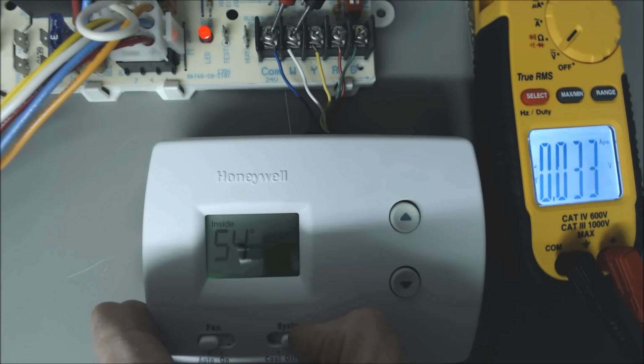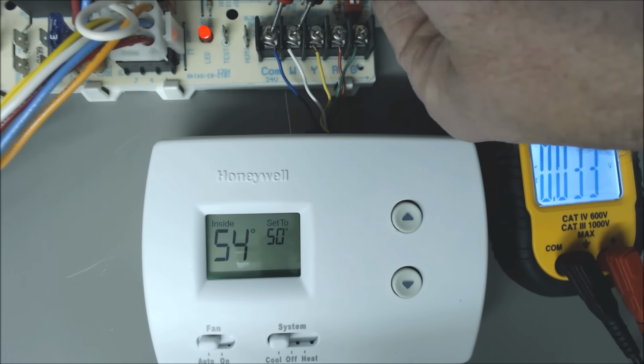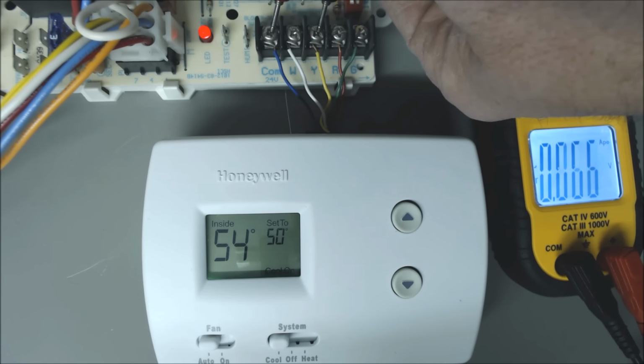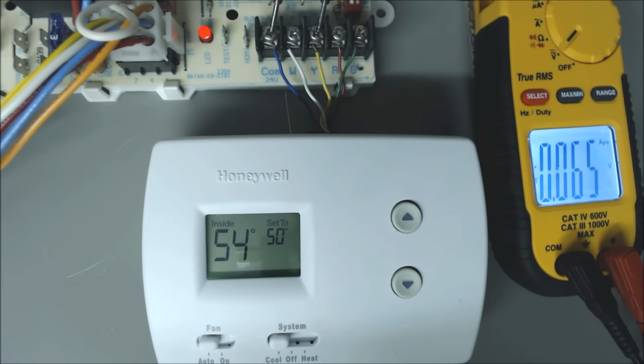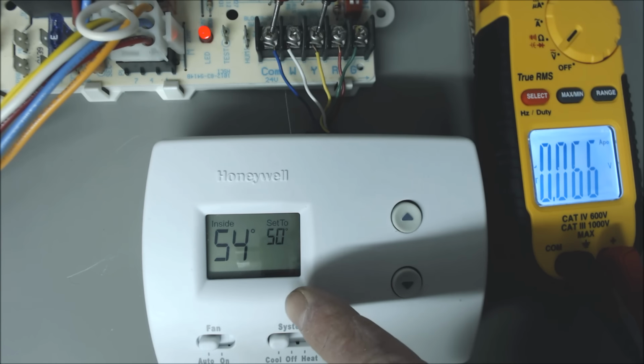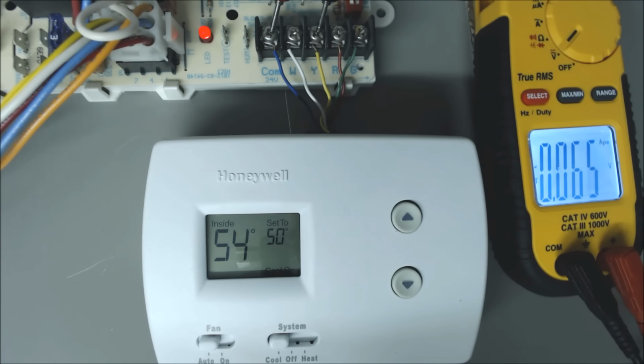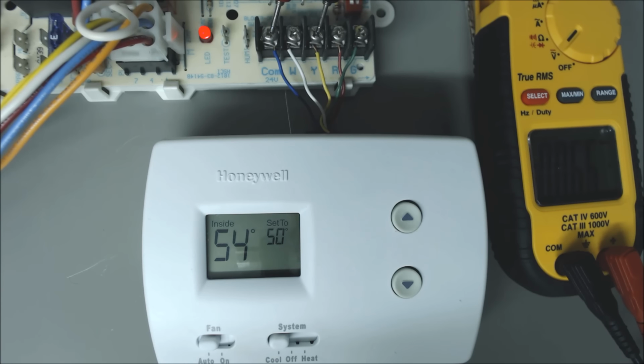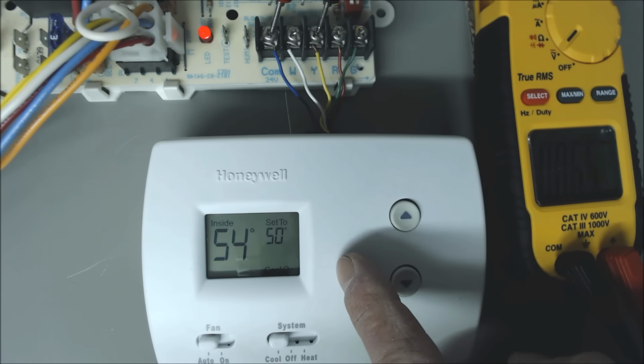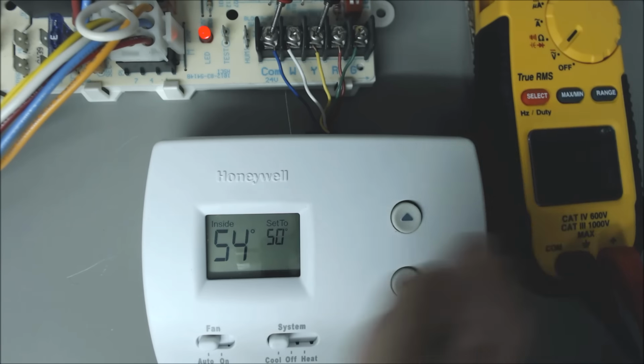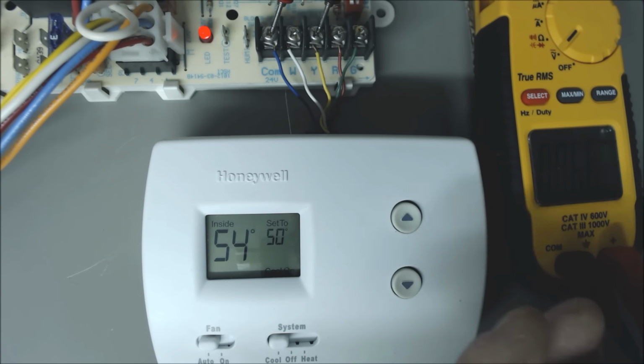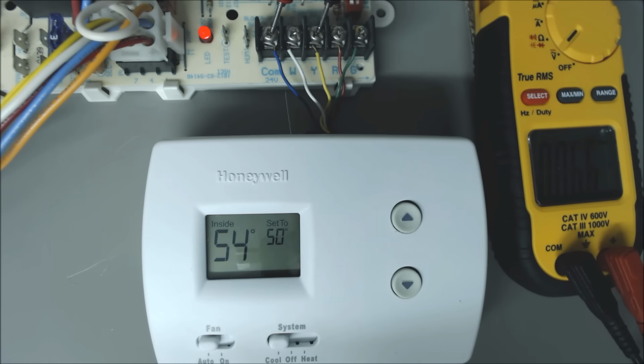Now we're going to go ahead and turn our thermostat to cooling, and we're going to leave the one probe on common, and put the other probe on Y this time. You see that we don't have any volts right now, and you see that cool on is actually flashing. That's a 5-minute delay before it's even going to turn on. Say you have just turned the power off to a furnace and just turned it on, the thermostat is going to see that. Or if you were running air conditioning or the heat pump, you turned it off and then wanted to turn it back on right away, you're going to have a 5-minute delay before it's going to kick in.